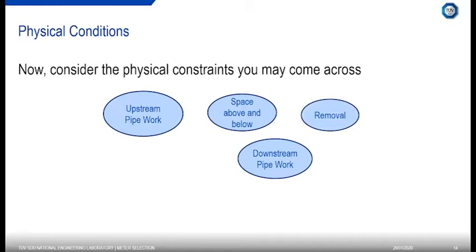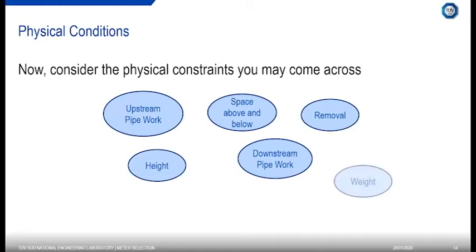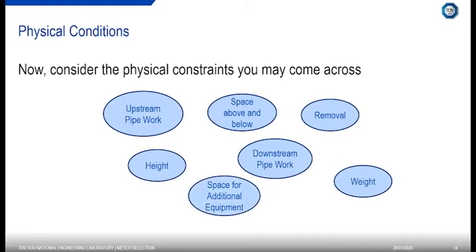Flow meters are regularly recalibrated — that's one of the main areas of business at NEL. You have to consider how you'd remove the device for calibration or routine maintenance. Consider the height of the installation, how you'd access it, and the weight — a large bulky device may require a crane. When installing a flow meter, you're not simply installing the measurement technology; you're installing other additional equipment that also requires physical installation considerations.